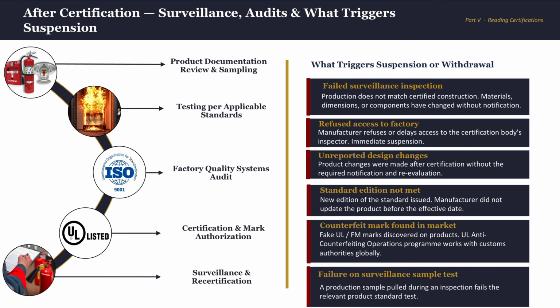Moving ahead, let's say I got my product tested and certified. Is that the end of the line? Definitely not. Product certification is not something you do once and then put in your company portfolio or on your catalog. No, it's an ongoing relationship between the manufacturer and the certification body, enforced through a structured surveillance program. You can see the simplified cycle because it goes deeper than this.